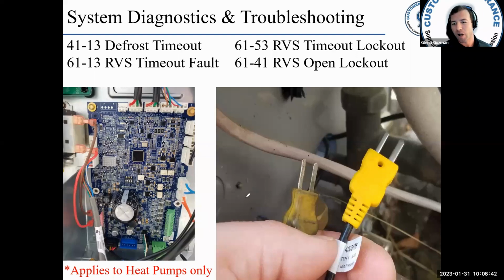But if I buy it brand new out of the box and I plug it in without testing it, you can get into trouble. I've bought brand new temperature clamps, clamped them on some ice, stuck it in ice water, and read 35 degrees. Now, for me, I have to take into account 3 degrees extra every time I measure a temperature. So some meters you can calibrate, some you can't. You've got to know your tools.